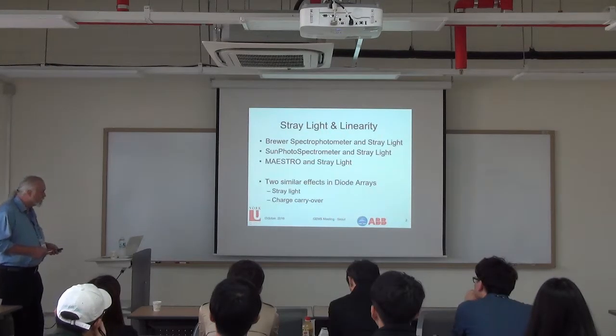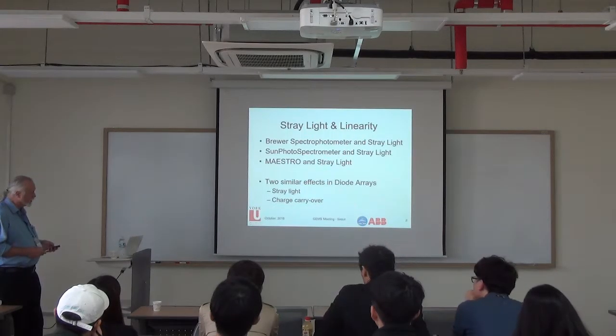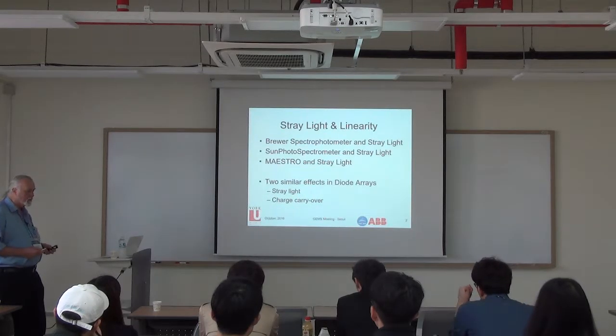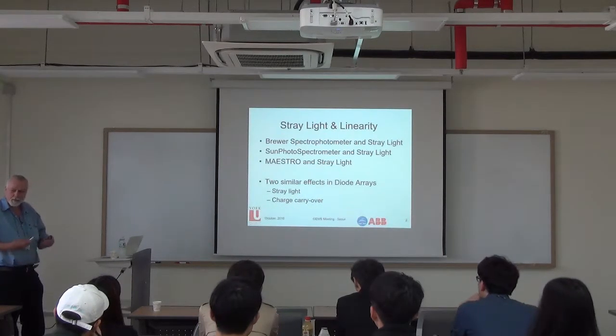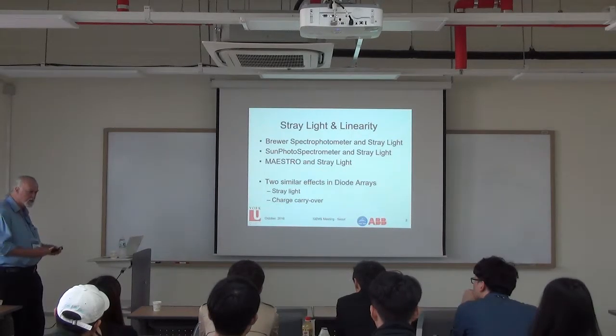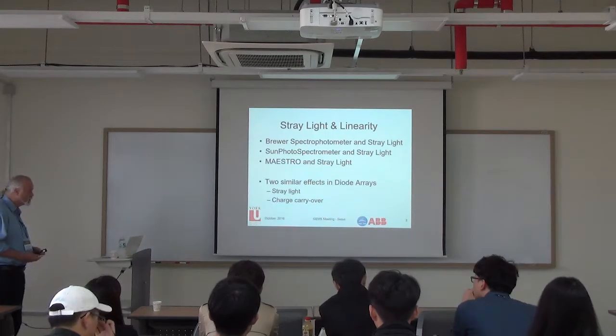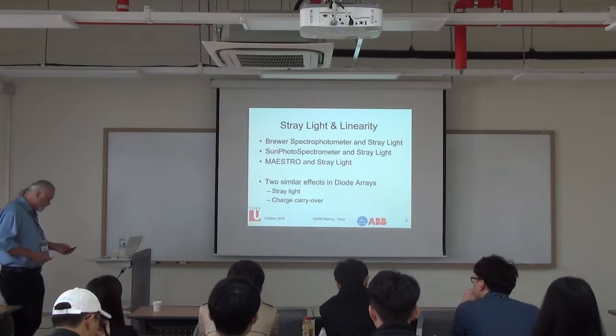One complicating issue is that depending on the detector you're using, you can actually have two different effects: one being stray light, and the other being the question of whether you're completely resetting the array before you make a new spectrum. They're related because both add a background to the measurement, and you need a strategy to distinguish between them, or at least understand what to do with those two different issues.